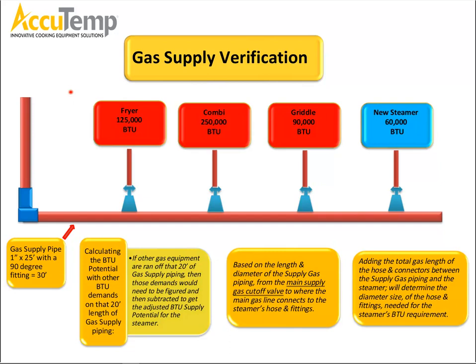Now, there are situations, as far as AccuTemp, where we'll have a customer that has issues with their equipment, and we will dispatch a technician and ask them, please map the gas. And mapping the gas is exactly what you see here. How big is the line and what else is hooked up to the line? On our startup form, we'll ask you to record the gas pressure with everything on the line running. But as far as a gas map, if you're asked, this is what we're looking for: what's on the line, how big is the line, and we need to see how much it can support. And yes, there have probably been more times than we'd like where, based on the current setup, that piece of equipment wasn't able to run correctly because they just did not have the correct volume.